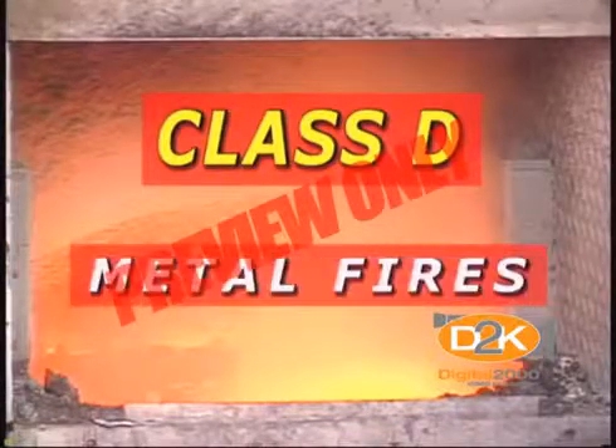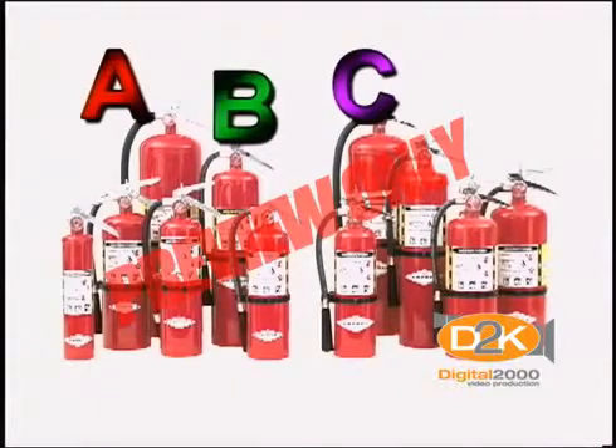If you use specialty metals such as magnesium or powdered aluminum, a class D extinguisher would be used to cover the metal fire with special powder until it's extinguished. In most shops, you'll probably see an ABC-type extinguisher, which can be used to extinguish all types of fires except class D metal fires.